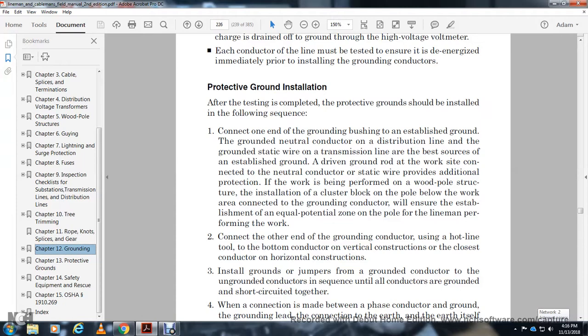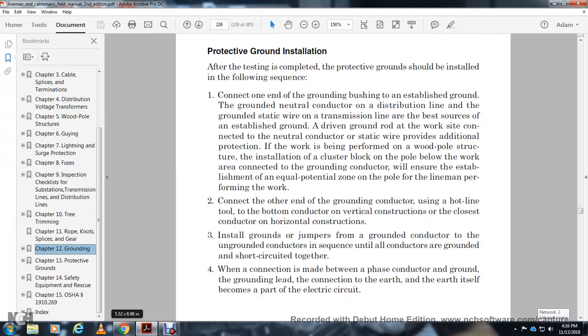2. Connect the other end of the ground conductor to the hot line with the bottom of the conductor in vertical construction, or the closest conductor in horizontal construction. Install the ground jumper of the ground conductor to the ungrounded conductors in sequence until the conductors are all conductively connected with the ground and short circuited together. When a connection is made with a phase conductor with the ground lead, the connection with the earth itself becomes a part of the electrical circuit.